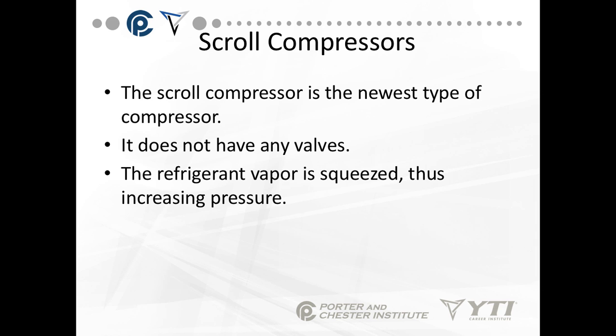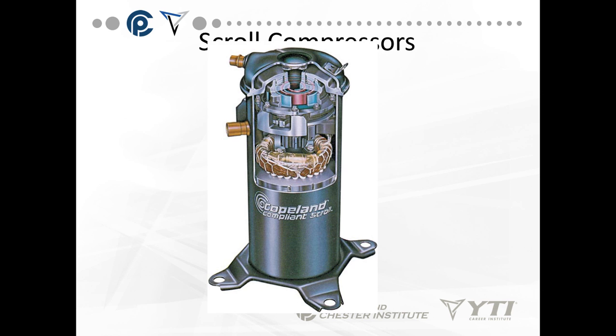The next type of compressor is the scroll compressor. It's not a piston action — the scroll compressor is the newest type of compressor. It does not have any valves. Think about a car engine or an air compressor that uses valves and pistons to move refrigerant and increase pressure — the scroll compressor doesn't have valves. The refrigerant vapor is basically squeezed through a scroll like a rolled-up piece of paper, thus increasing the pressures.